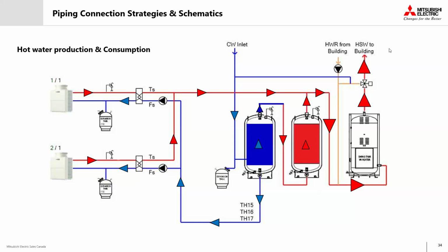Once our hot water production from the heat pumps outpaces the demand in the building, at the tail end of our peak demand period, the storage will begin to be recharged. One of the key concepts to wrap your head around here is that the flow path through our storage tanks, through these stratified tanks, is capable of reversing flow depending on the operating conditions out in the building.